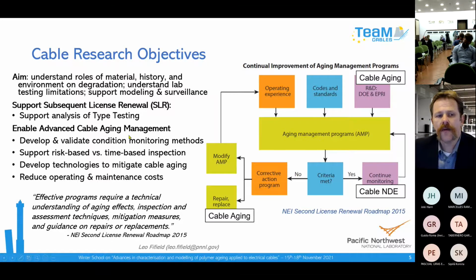So what I want to emphasize is that in the original qualification for 40 years, safety-related cables were qualified for 40 years. And the way that they qualified the cables before the plants came online at the beginning was to do accelerated aging in the laboratory at elevated temperatures and high dose rates, to impart an effective 40 years of aging on the cables, and then do design basis event testing, loss of coolant accident testing, to see if the cables will survive that. And if they had the 40 years of equivalent aging and then they survived the testing, then they could be qualified. But as I'll mention, that process that was used to get the 40-year qualification life is being looked at with greater scrutiny, in more detail, as we try to take these cables and these plants beyond their original intended life to 60 and 80 years.